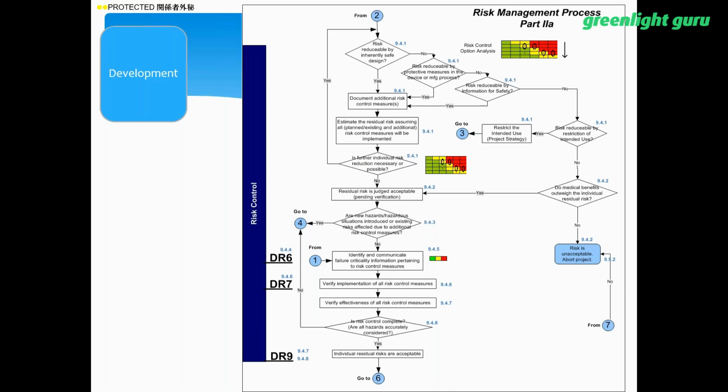That's a qualitative term. In that qualitative term, my experience has been that when the FDA comes in and does an inspection on your design control process and they go through your risk management file, they're going to look at what is the technical work that you have done and what is your technical rationale. If that technical rationale makes sense as coming from your technical folks, I haven't seen them challenge that too much in the areas of is that as low as practical, okay?